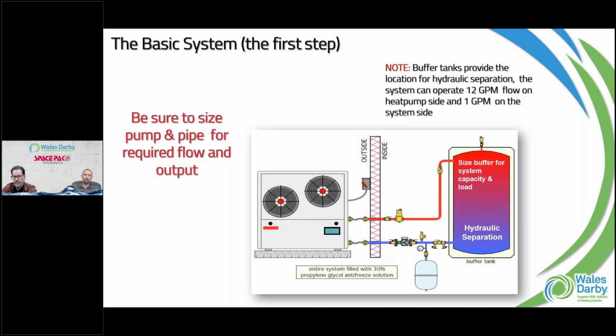So we could technically give you simultaneous operation, maybe putting some heat into the floor as tempering while running a dehumidification system with cooling. We can do that at the same time because the outdoor unit sees which tank needed its temperature back first, heats or chills it down, and once satisfied, moves over to the other tank. The control strategy and the outdoor unit work together to make sure the buffer tank, or multiple tanks, are always satisfied.